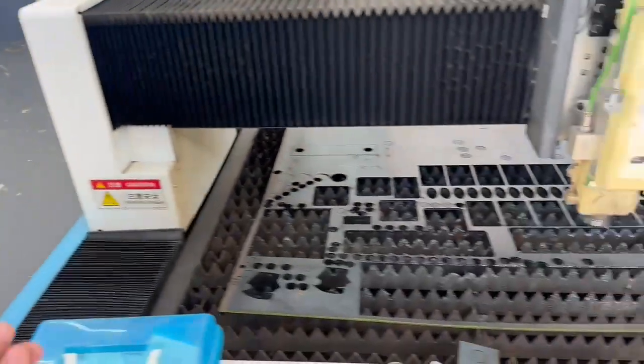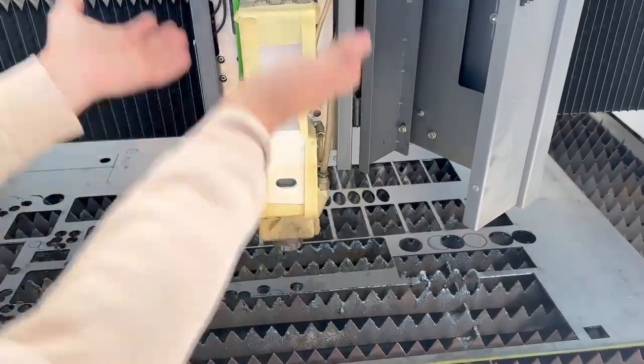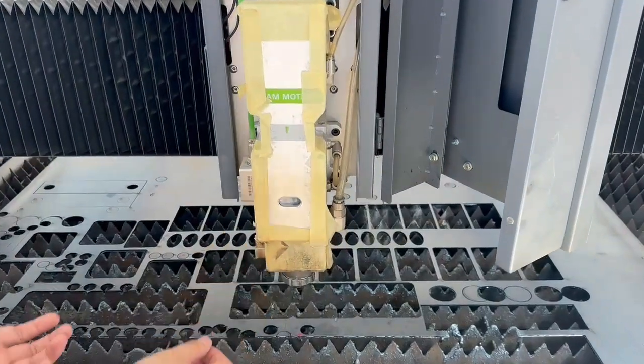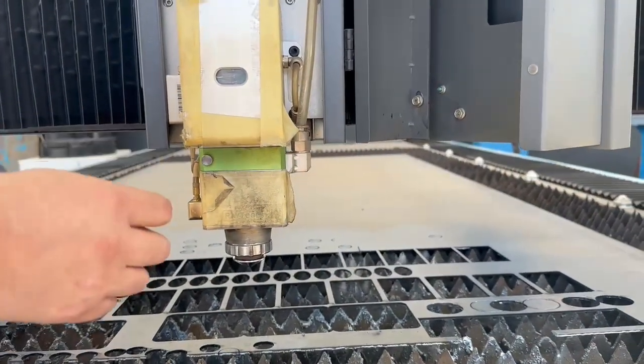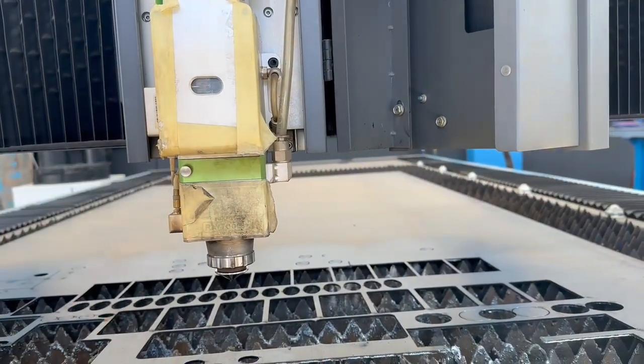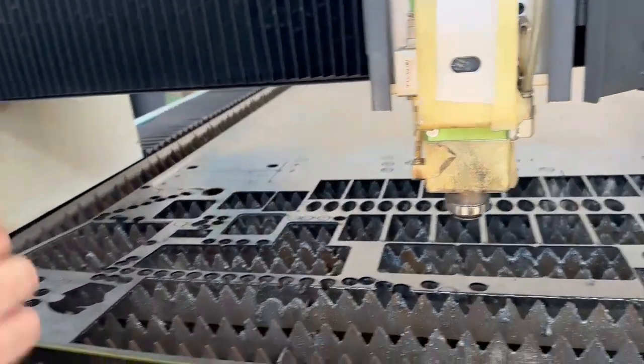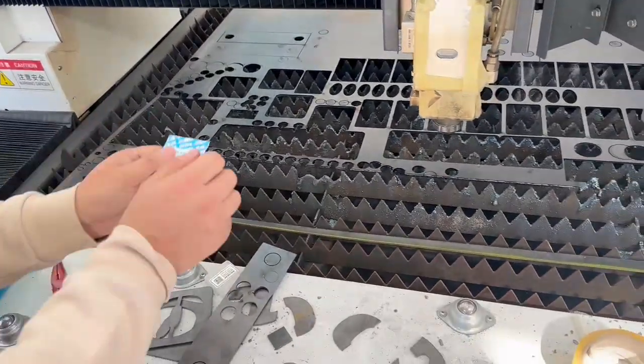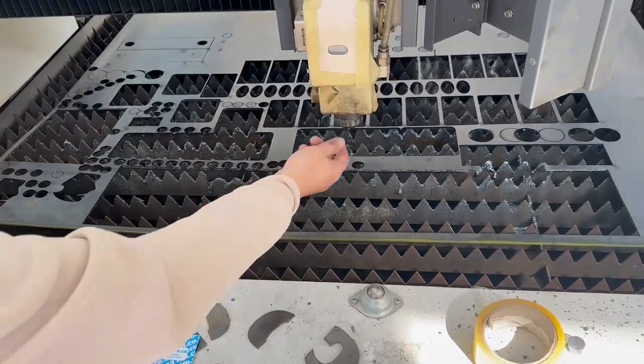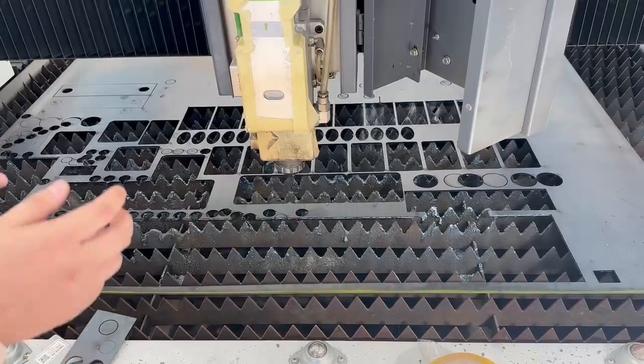So very important is do not touch anything above. Only check this lens. If it's clean, put it back quickly. If it's dirty, you change it. Use the wipe carefully. Make sure you do not introduce dust to the system.